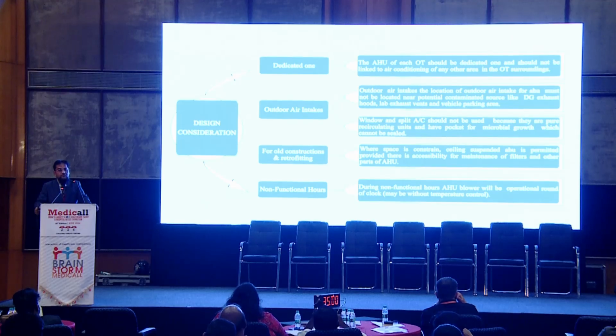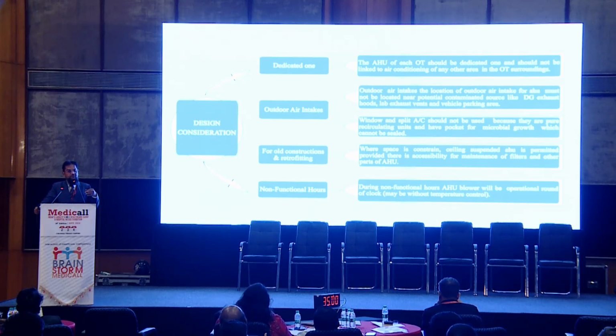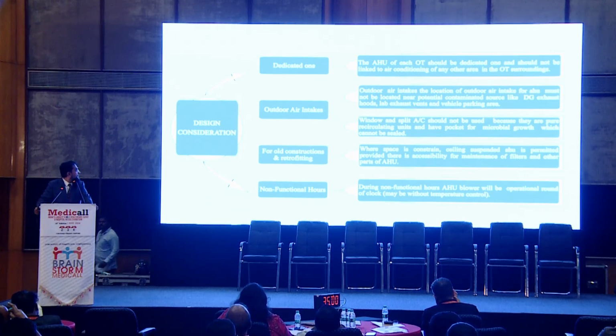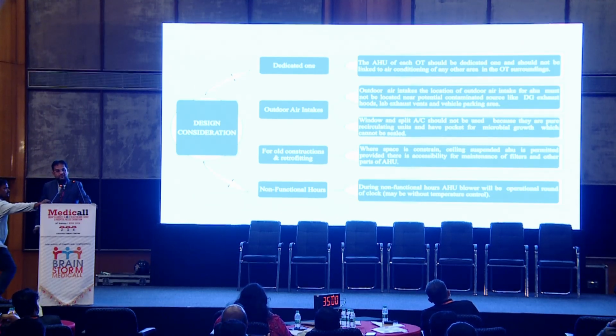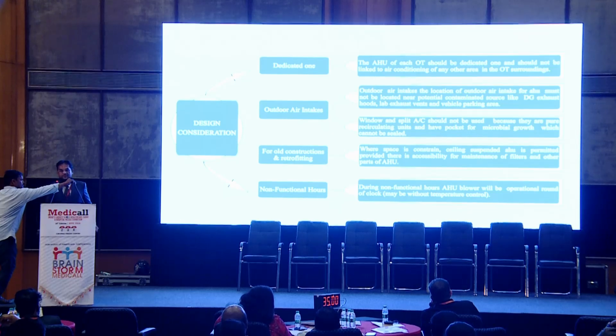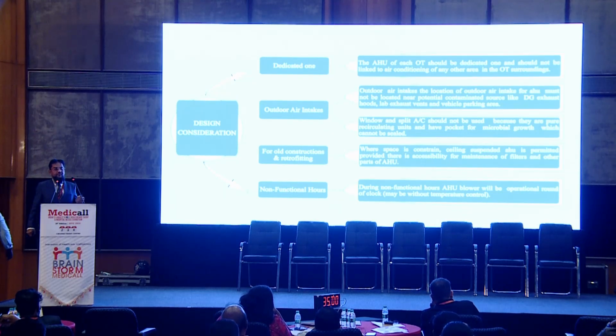They said that window or split ACs should not be used in any type of operation theater, because they are pure recirculating units. What will happen? You cannot maintain sterility with that, because they only recirculate the internal air. Okay. And further, they said that where space is constrained, a ceiling suspended AHU is provided. There is accessibility for maintenance of the filter and other parts of the AHU.